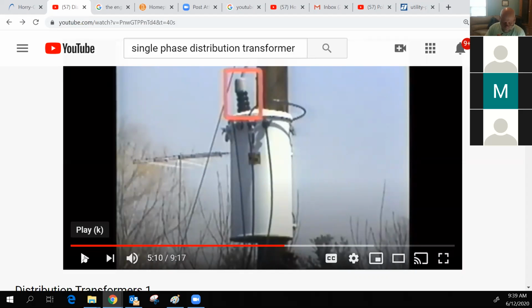Okay, and while you're still sitting there, Professor Vermelin, different companies have different techniques. Santee Cooper does not use these types of transformer, obviously by the ones you've seen out there in the field. This transformer, and you just looked at it in your previous quiz, you've got to have a complete path both on the primary and secondary sides for you to be able to get voltage to flow. So some companies use this technique of the secondary neutral making the complete path for both primary and secondary. Santee Cooper doesn't do this. It uses a dual primary bushing scheme. So you have a path for primary and a path for secondary that are separate. Right.